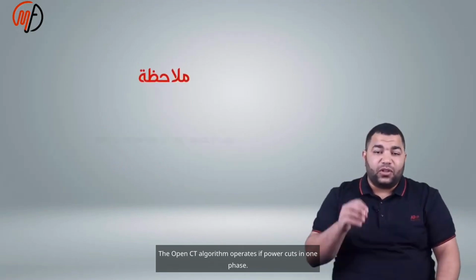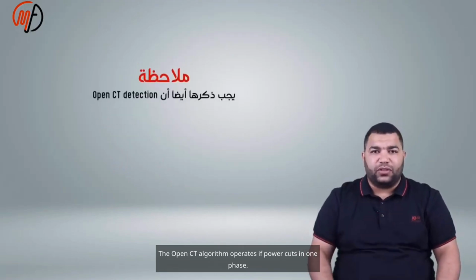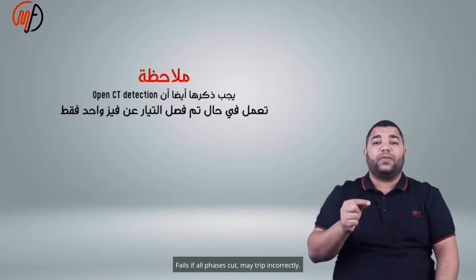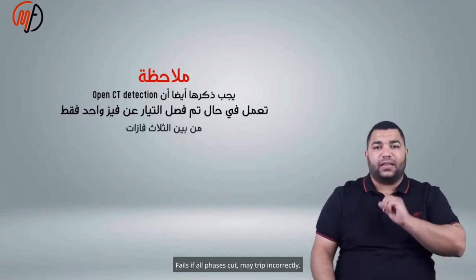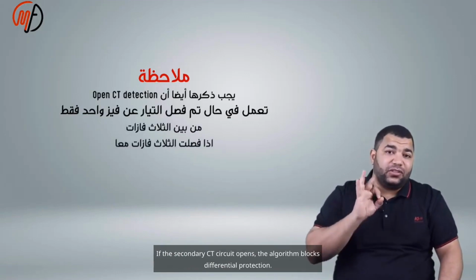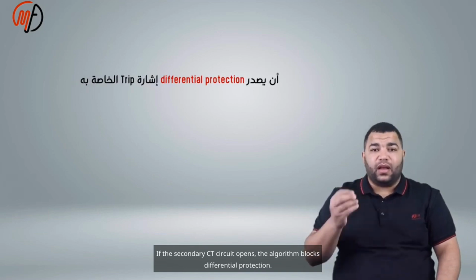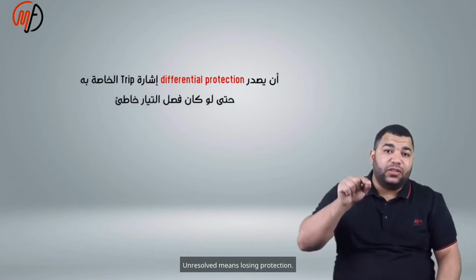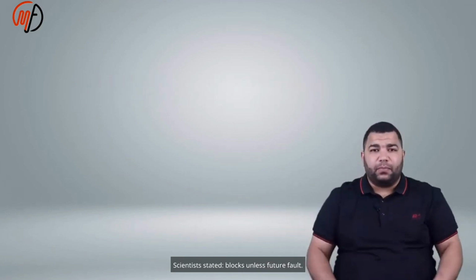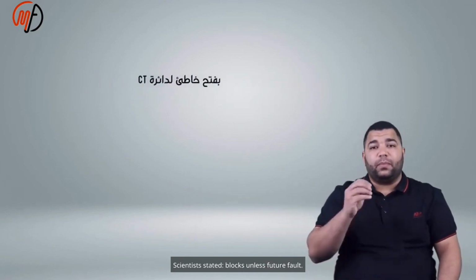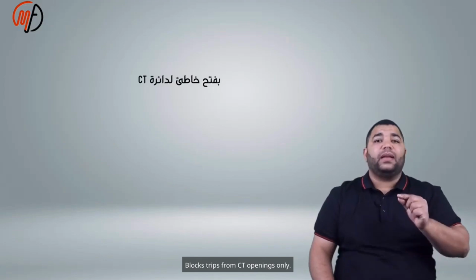The open CT algorithm operates if power cuts in one phase. It fails if all phases cut, and may trip incorrectly. If the secondary CT circuit opens, the algorithm blocks differential protection. Unresolved, this means losing protection, so it blocks unless a future fault occurs. It blocks trips from CT openings only.